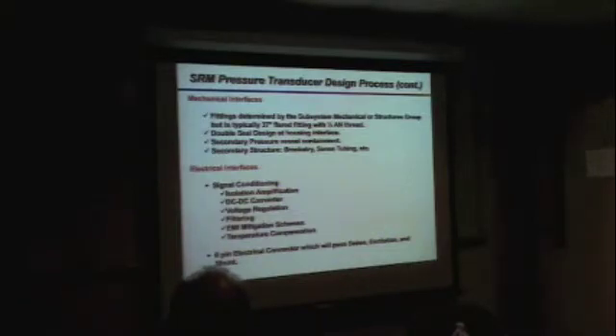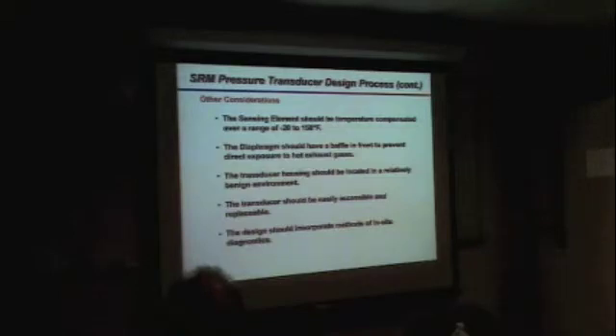Then what are the electrical interfaces? Is the sensor going to have signal conditioning inside of it? If so, it's going to have to have all these features. And then you'll have a 6-pin electrical connector. So here are some other considerations. The sensing element should be temperature compensated. The diaphragm should have a baffle in front of it to prevent direct exposure to hot gases. The transducer housing itself should be located in a relatively benign environment. And the transducer should be easily accessible. And the design should incorporate methods of in situ diagnostics. Now, one method would be the shunt resistor.